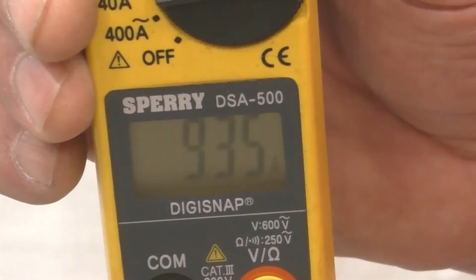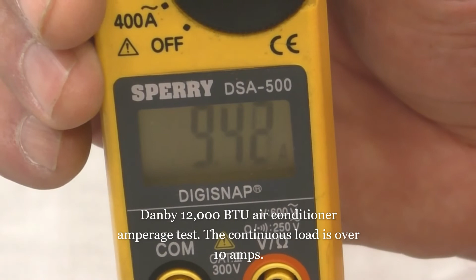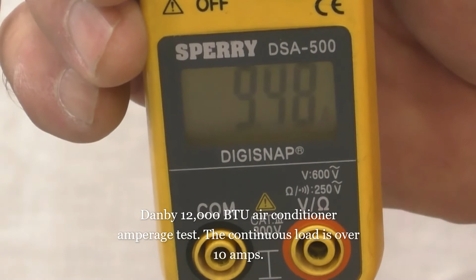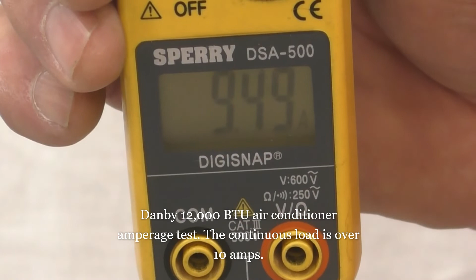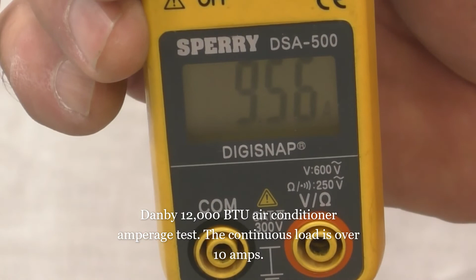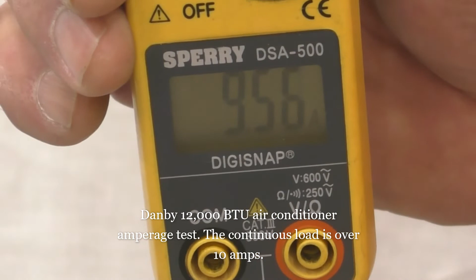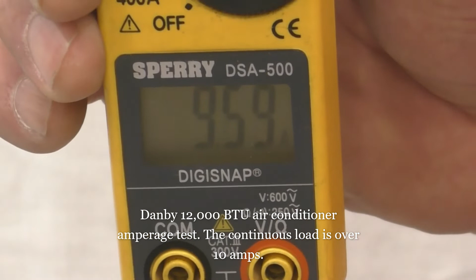A 1,500 watt heater, and it brags about 1,500 watts. Well, you've got to do your own calculations. Divide it into 120 and find out what you get. If you have 9 amps or at least 8 amps, and over 8 amps, it needs a dedicated 20 amp circuit. It shall have it. If it's over 5 or 6 amps, and this is a unit that's going to be a continuous load. There's a difference between a continuous load and a quickie deal that you just put on and off. This is a continuous load, so if you calculate everything, anything 7 amps and over should have a dedicated 20 amp circuit.